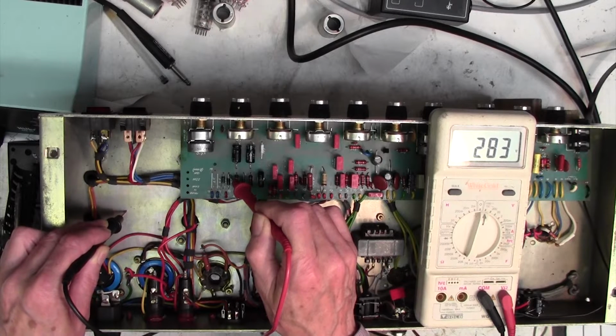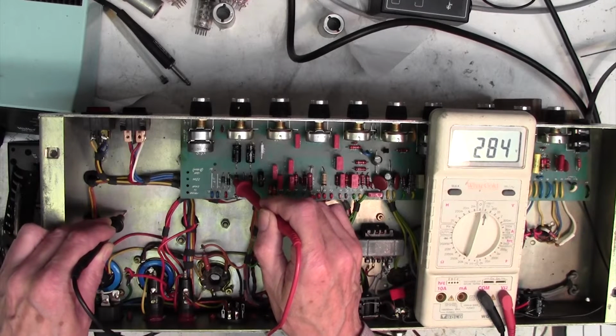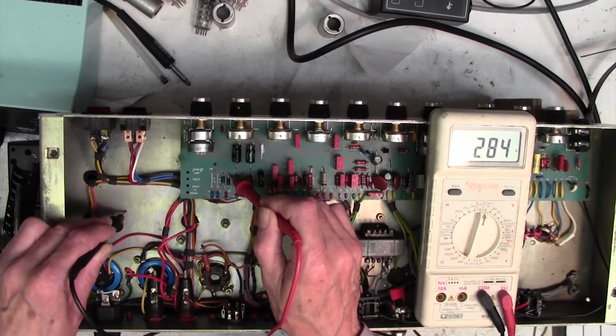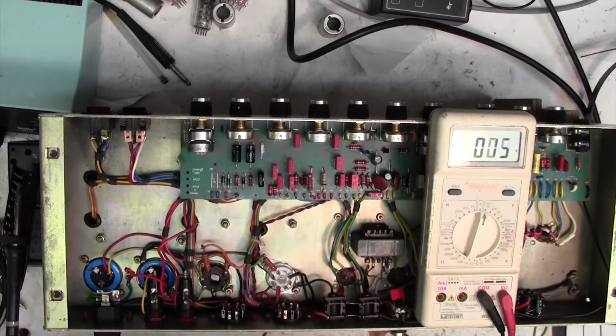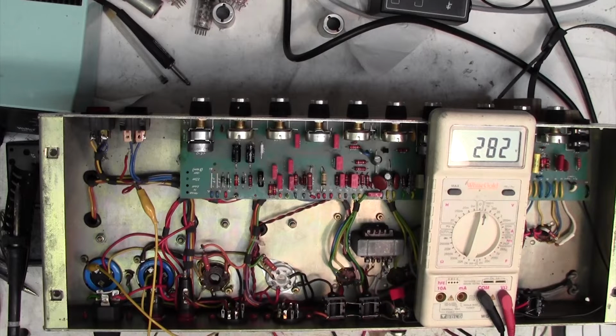Remember, we had 368 on the other transformer, so we're well down. We've disconnected everything downstream. So there you go, we've got a mains transformer which for reasons unknown is giving out a low HT voltage. I have no idea why that is. Could be a wrong transformer.